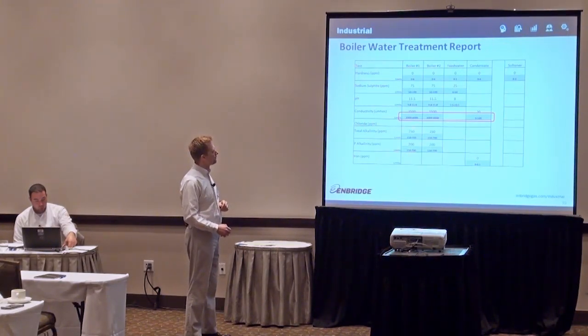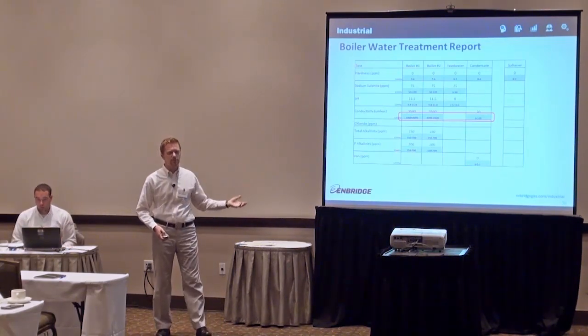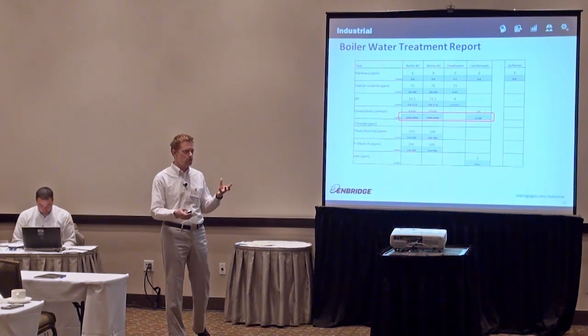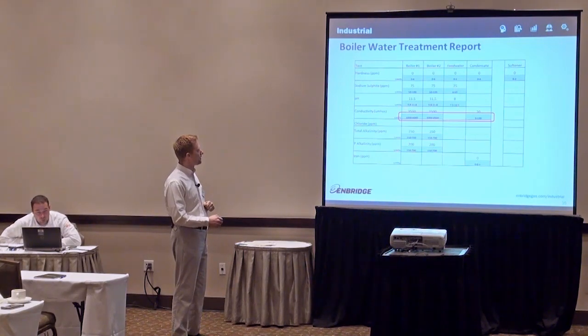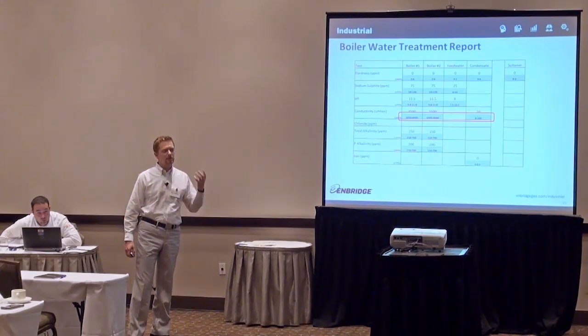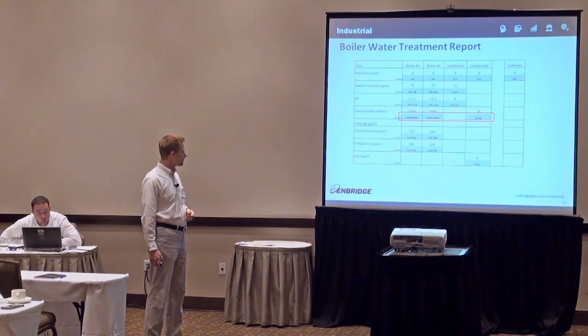So 3,000 to 4,000, again, there are a lot of variables that go into this. These are typical numbers. Your water treatment supplier is going to be the one that sets these things and knows the finer details behind what's going on there. But you want to make sure that the number you're seeing on your report is in the range of the limits that have been determined. And if you've got that automatic blowdown control from your boiler, it's keeping it in that range.